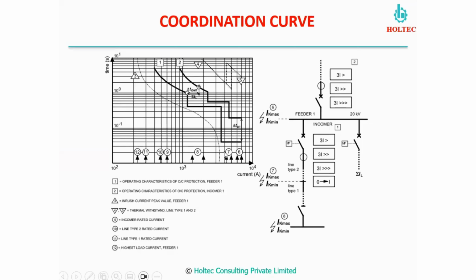So the moment the current will be less, the fault time will be high. In that way we can get this graph of relay 1, the characteristic curve. The same way we can also achieve the relay characteristic curve for relay 2, and with the help of the software, we can do the proper grading.